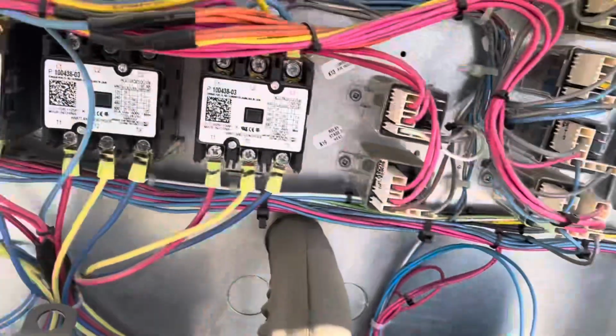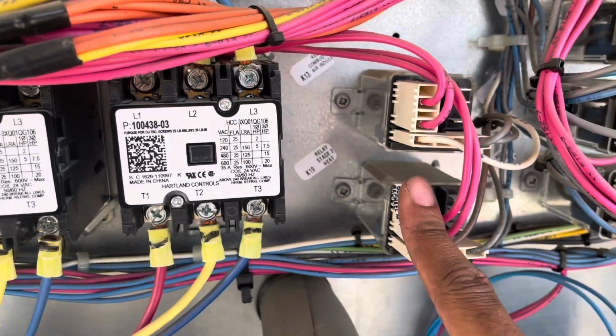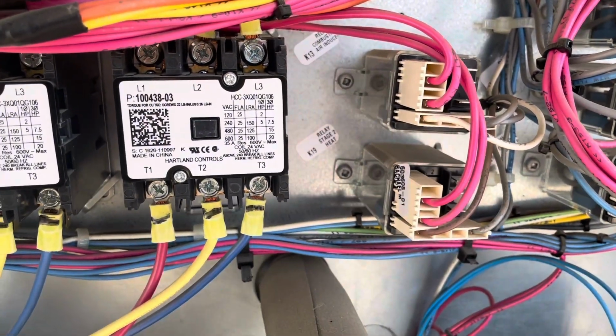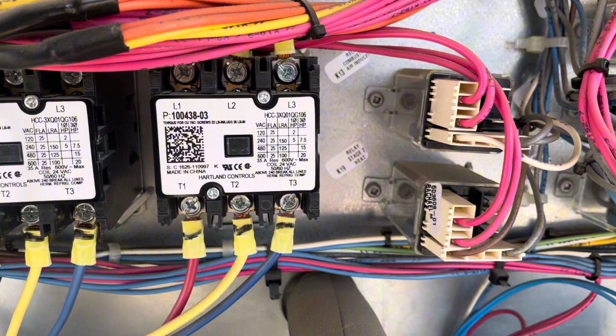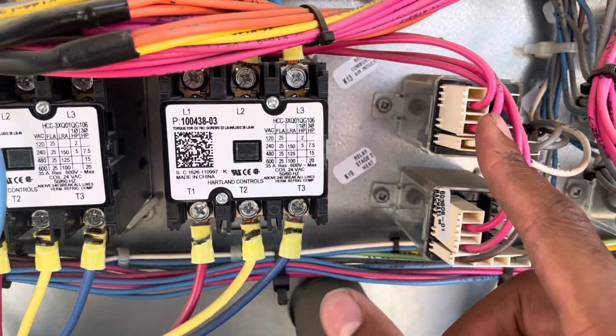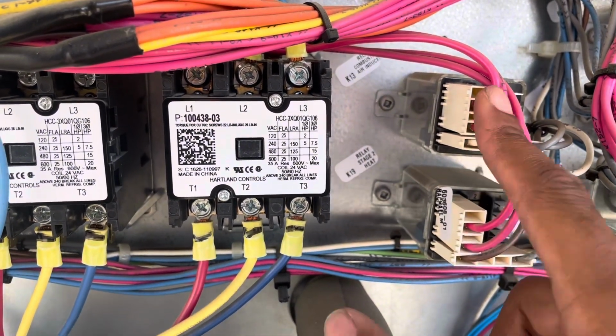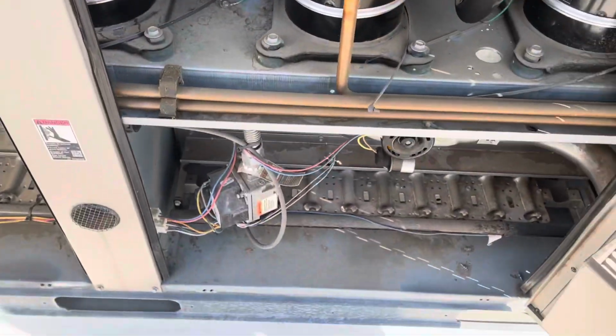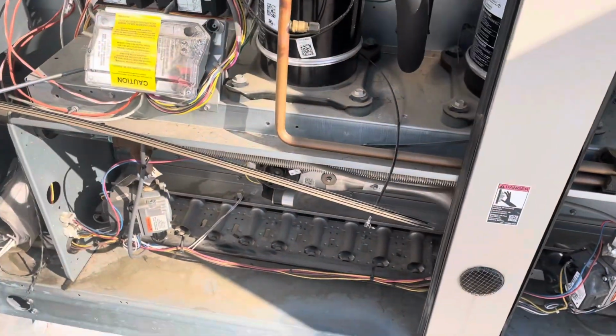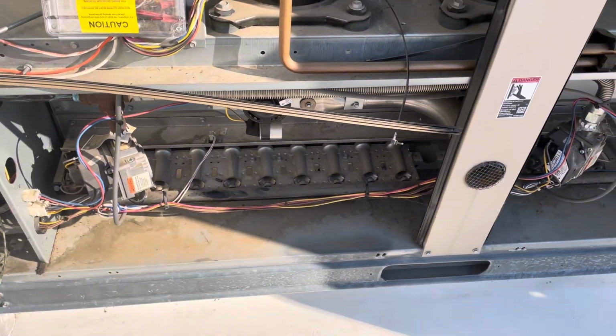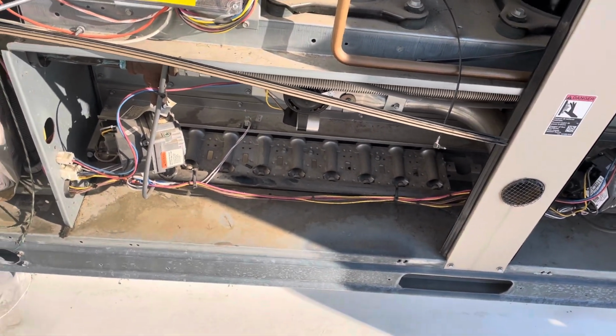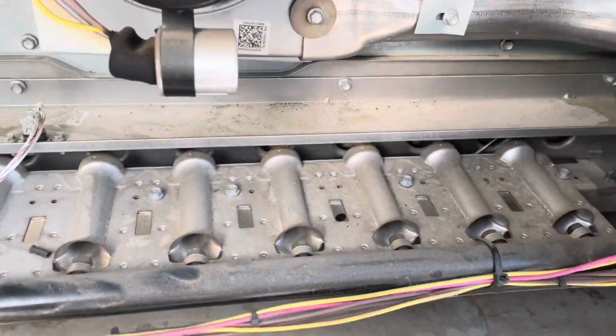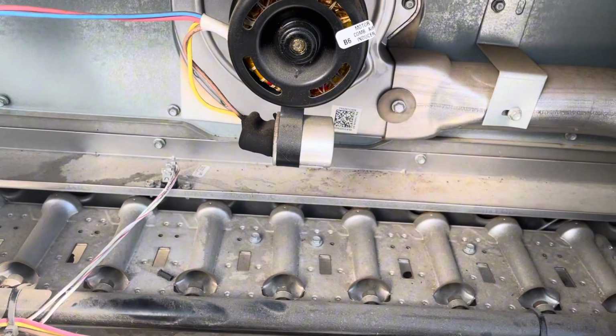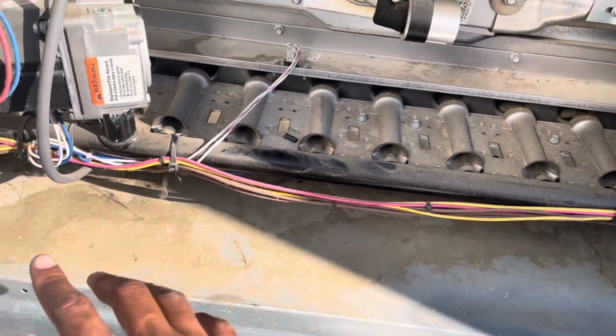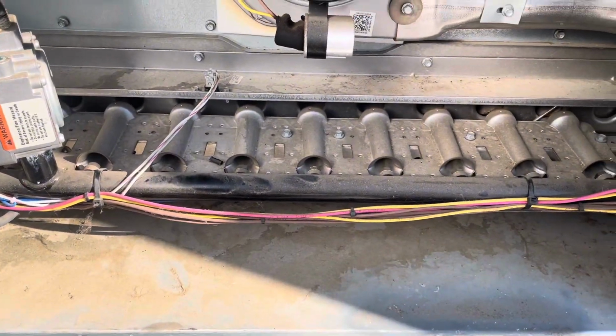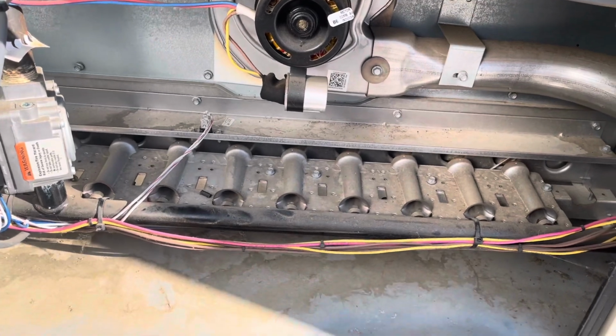Now up here at the top, you have your 2 ice cube relays for your inducer motors. So whenever you get a call for heating, 24 volts energizes the coil, and then the contacts close and you have high voltage being sent to your inducer motors. So when you're doing a heating PM, the things that you want to do, first off, is to make sure that the heating section or compartment is clean.